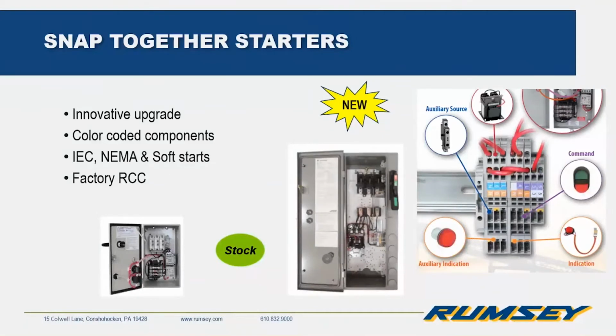So here we have snap together starters. So what Rockwell did when they released this, they gave an innovative upgrade to some product that has been around for a long time. It's well known. Enclosed starters, combination starters, a lot of people use them. And this was a nice upgrade to help with installation and replacement of parts. So on the right here, you see the plug-in module. And this plug-in module comes already pre-installed inside the enclosure with the contactor and disconnect.